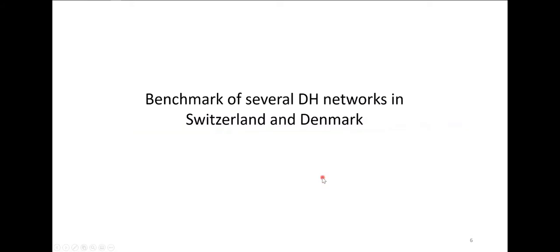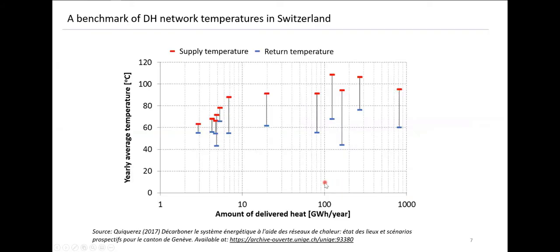Looking at the situation in Switzerland, here is a benchmark of 12 district heating networks, showing in red the average supply temperature and in blue the return temperatures. The x-axis represents the amount of annual heat delivered — small networks on the left, large ones on the right. We see temperatures ranging from about 65 up to 110 degrees, and nearly all return temperatures are higher than 50 degrees. There's no clear relation between network size and temperature levels.